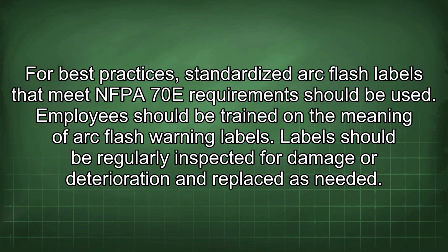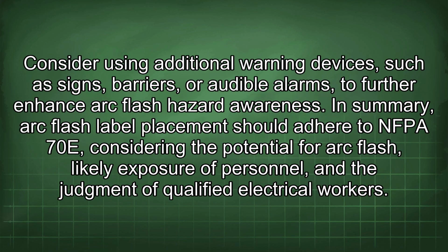For best practices, standardized arc flash labels that meet NFPA 70E requirements should be used. Employees should be trained on the meaning of arc flash warning labels. Labels should be regularly inspected for damage or deterioration and replaced as needed. Consider using additional warning devices, such as signs, barriers, or audible alarms, to further enhance arc flash hazard awareness.